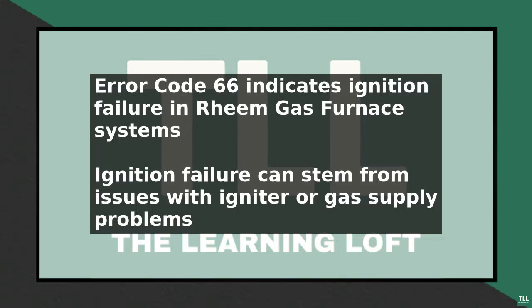Rheem gas furnace error code 66 is an indicator of a specific issue with your furnace. Understanding what this code means and how to address it is crucial for maintaining a functional and efficient heating system. First, it is essential to recognize that error code 66 refers to an ignition failure, which means the furnace is unable to ignite the gas to produce heat.